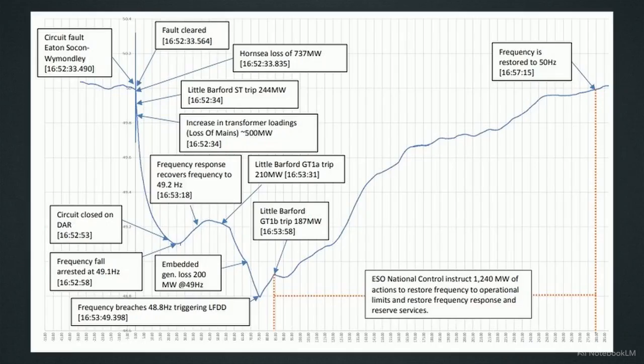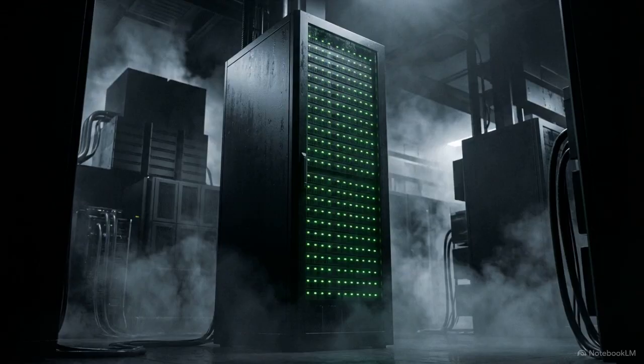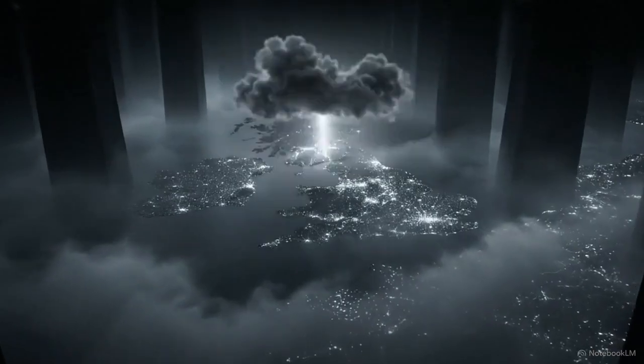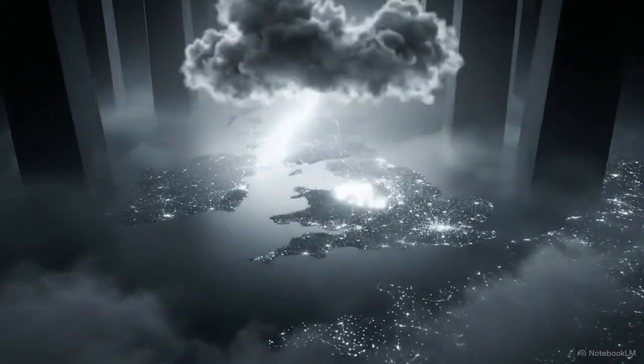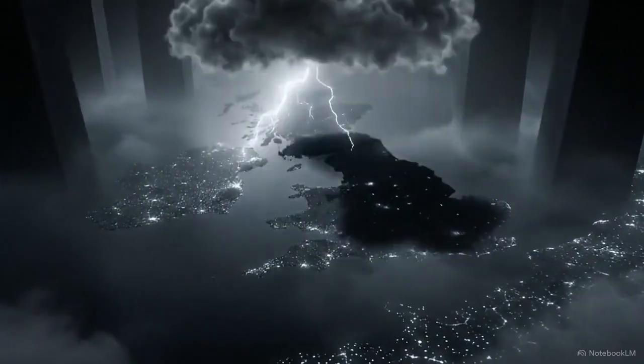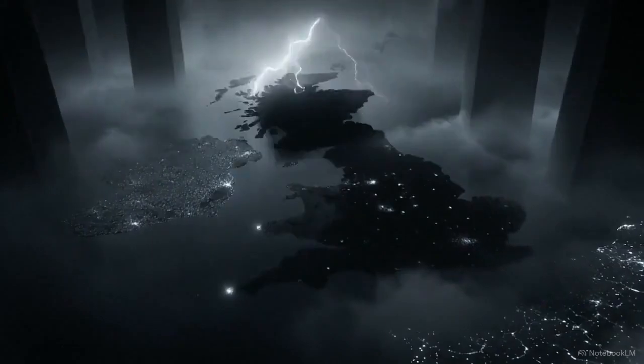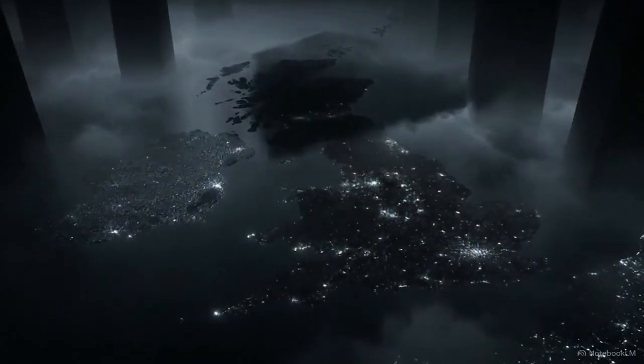This chart's sharp drop shows the initial 1,300 megawatt loss from Hornsea and Little Barford, burning through the grid's reserve. This frequency drop triggered localized embedded generators, like solar and diesel, to automatically sever from the grid, erasing another 500 megawatts. Every piece of physical hardware was fully functional, but isolated software systems across the country, programmed to protect specific equipment, reacted to the anomaly by shutting down, creating a massive collective power deficit.